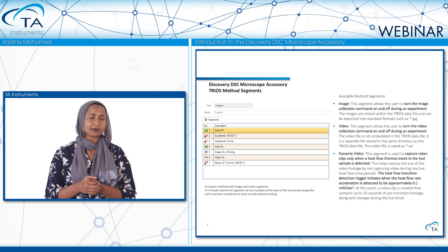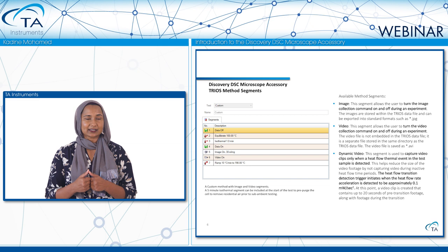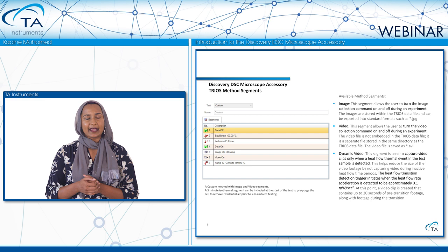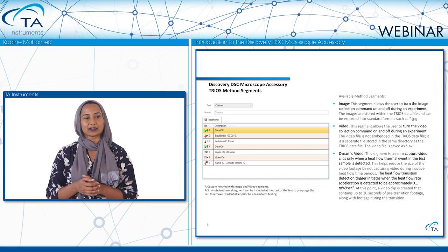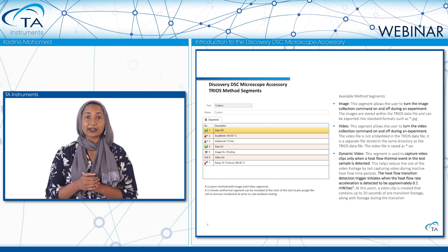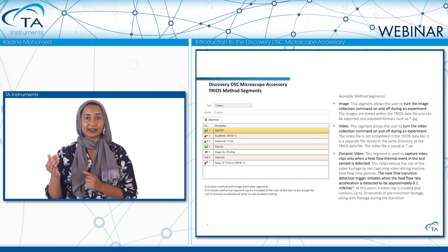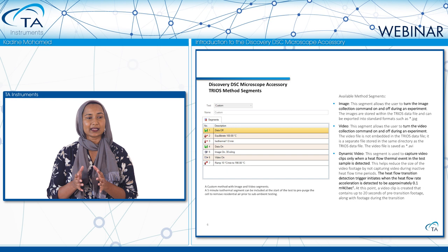The video segment allows you to turn video on and off during the experiment. Video files are not part of the TRIOS data file; they are stored as a separate file within the same directory. Dynamic video is a particularly nice feature — it captures video clips only when there is a heat flow thermal event taking place. The instrument tracks the heat flow signal and its derivative, and when the second derivative of heat flow exceeds 0.1 milliwatts per second squared, video collection begins. This reduces the overall size of the video file.